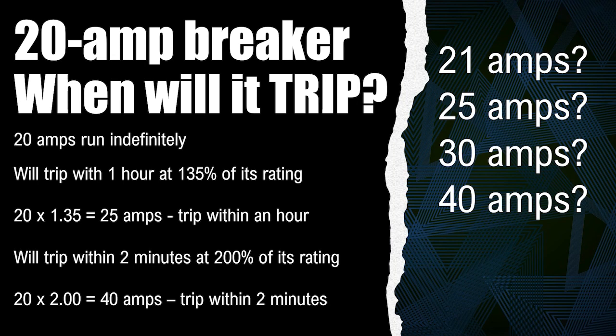Which makes sense — if we've got this very large current and it's just going to be for just a moment, maybe the startup of a motor, we don't want it to trip right away. What if your microwave fluctuates up for just a minute, then it comes back down? We want to be able to use our products without it being a nuisance all the time. Because if a product was a nuisance, a customer will just put a larger fuse or a larger breaker in there, and then we have a hazard.